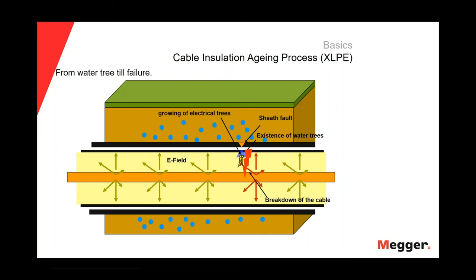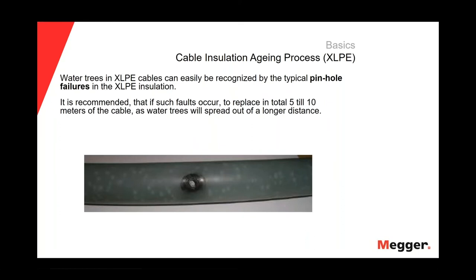So, continuing with the insulation aging process in XLPE cables. It's important to know that when water trees are in the cable, they can easily be recognized by typical pinhole failures in the XLPE insulation. For this reason, we recommend that if such failures occur, you replace between 5 to 10 meters of cable, as the water trees will spread out over a longer distance.